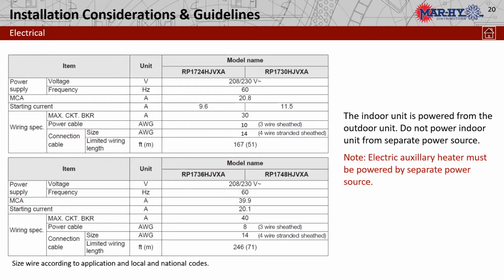Electrically, let's look at them. So the 24 and 30, the 2 and 2.5, we have an MCA, maximum circuit ampacity, of 20.8, and a maximum breaker size of 30. So pretty standard stuff. We look at the 3 and 4-ton. We've got an MCA of 39.9 and a maximum breaker size of 40. All standard stuff. Do remember that the electric strip heaters are a separate power source. The indoor unit does not share power with the strip heats. That is its own power.